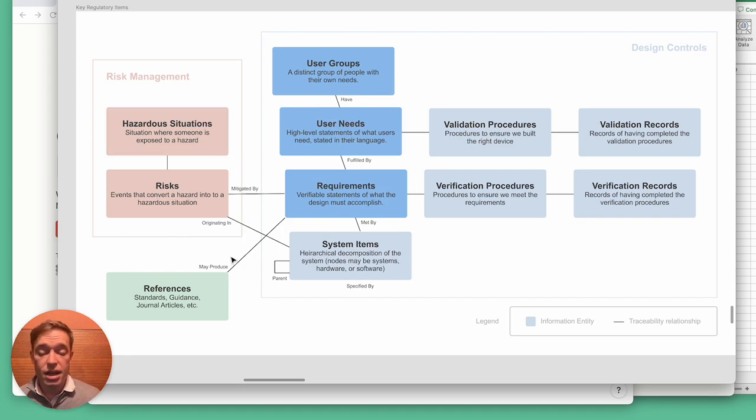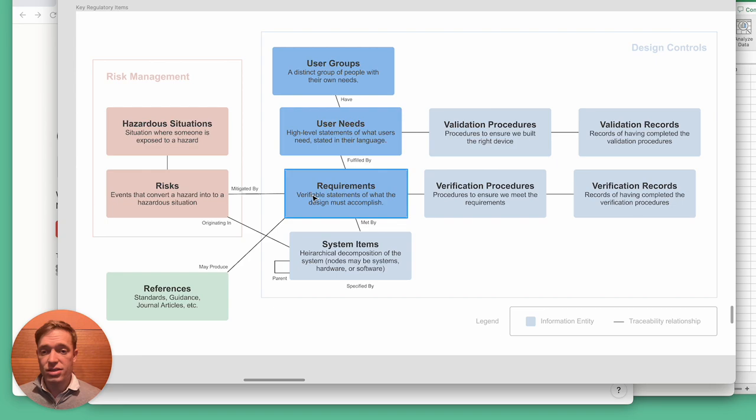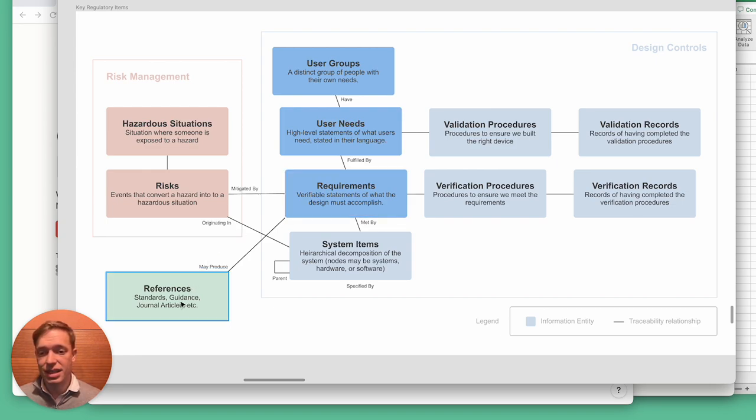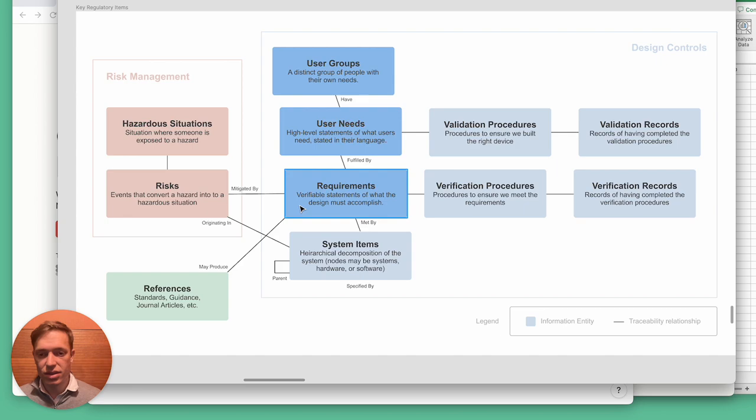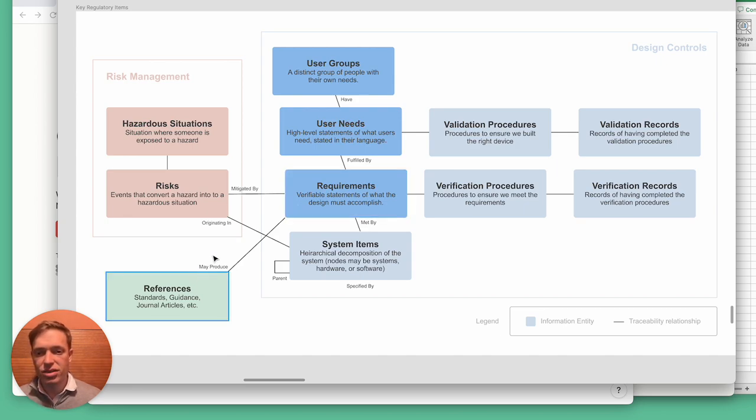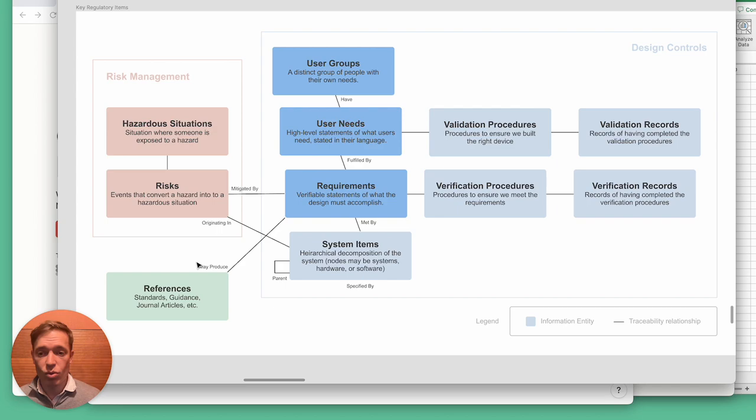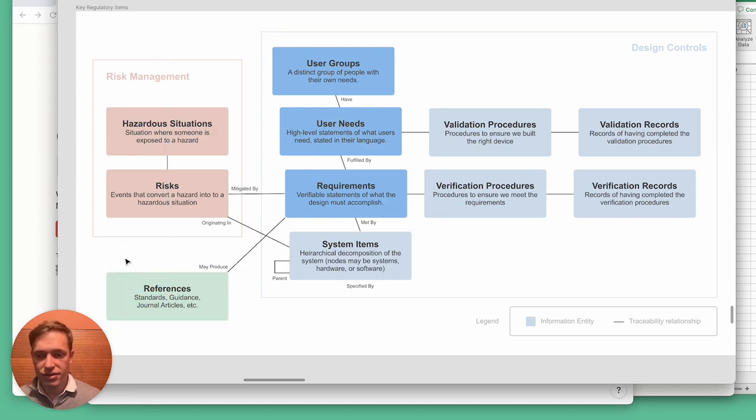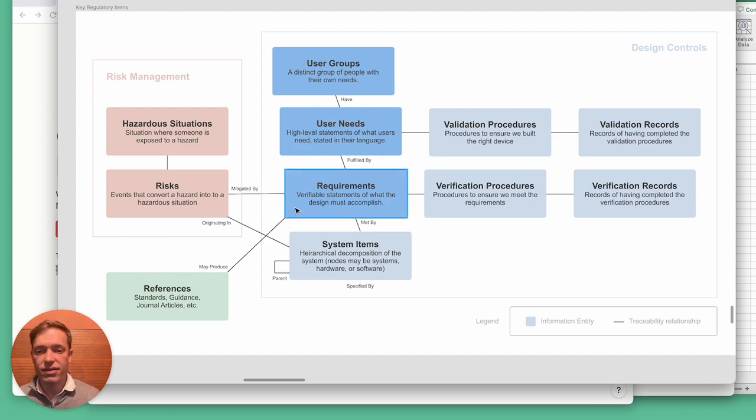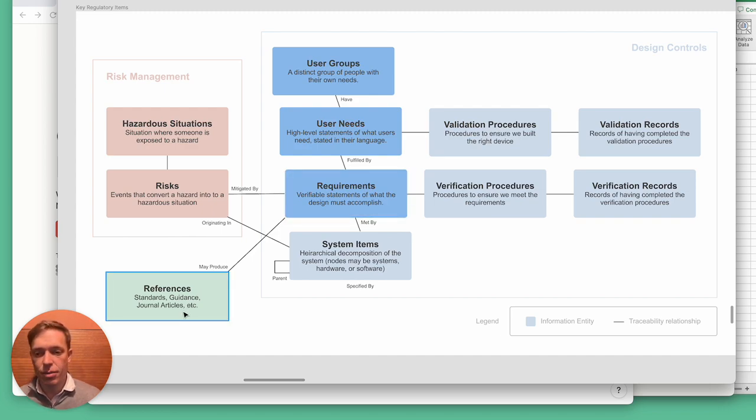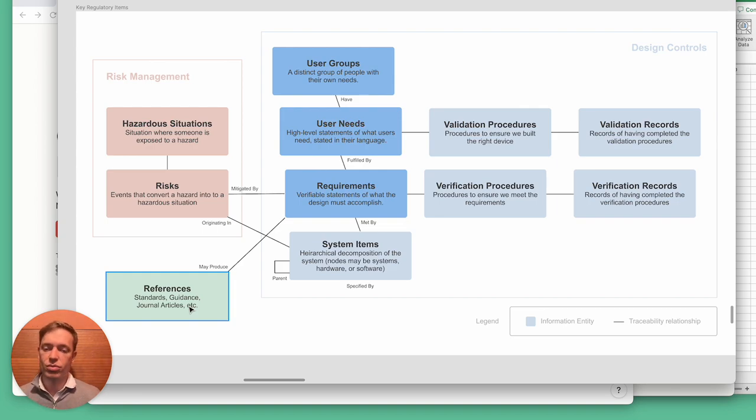Another example is we found it can be very convenient to trace requirements back to standards or guidance documents that are the source of those requirements. There are various ways you could do that—you could put them as a user need, but we actually have a bibliography that we use throughout all the documents we produce. It's very convenient to be able to trace the requirements that go back to, say, IEC 60601-1 or whatever other standard.